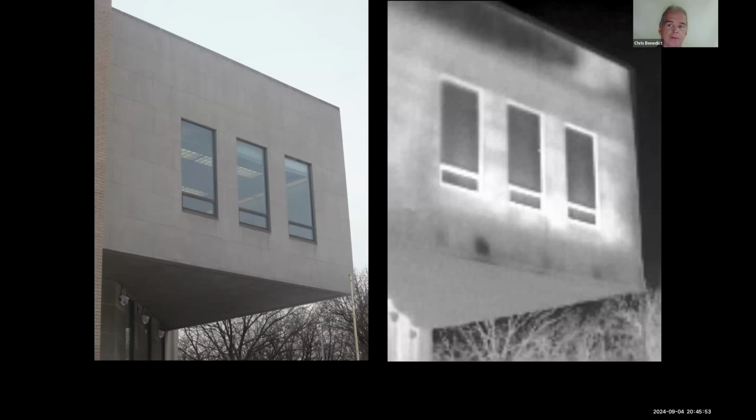This new part of the building has the misfortune to have an HVAC system where they attempt to deliver heating, ventilation, and air conditioning in one set of ducts, and all kinds of chaos results. So this system might be pressurizing the building, might not, but definitely the stack effect is going to be pushing air up and out there. The black spot below the windows might be water, or it might be cold air being sucked in. If it's cold air sucking in, then this part of the building is probably under negative pressure, the whole area. And despite being at negative pressure, air is still leaking out the top.